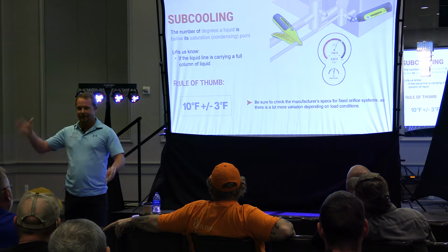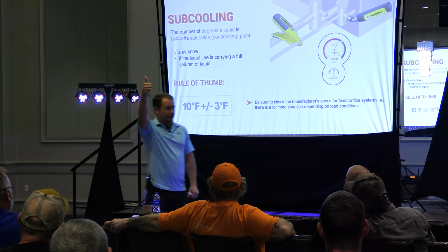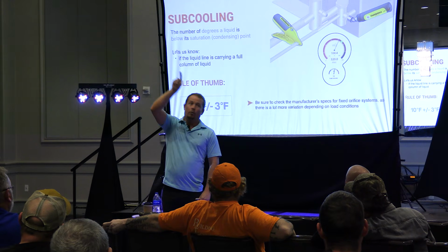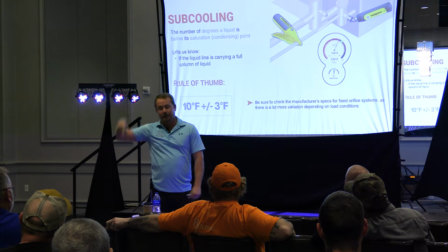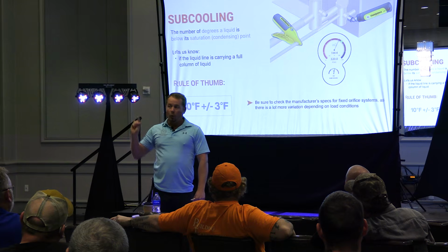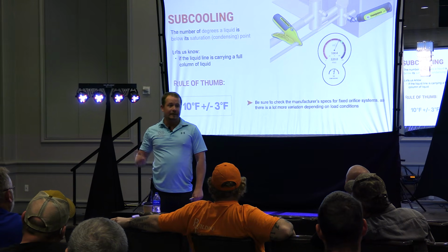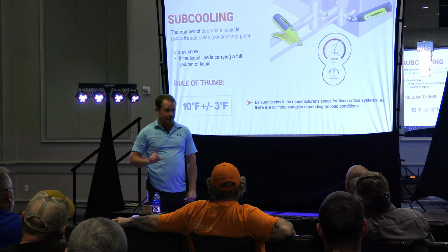They're confusing information. But other than those two things, making sure we have liquid quality, having enough subcool so it makes it up the wall and through the attic and all the way over and over the river and through the woods, and then it hits the metering device with liquid. Or if you're mechanically cooling it, other than that, increasing the subcooling does not help. It's not a good thing.